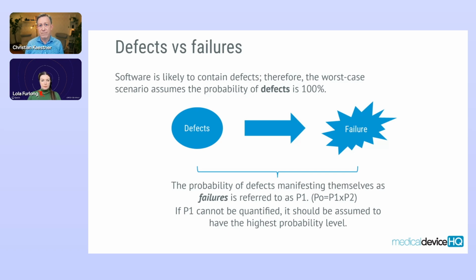The probability of defects manifesting themselves as failures is referred to as P1 when you work with risk management. Perhaps you're familiar with P1 and P2 concepts. If P1 cannot be quantified, it should be assumed to have the highest probability, meaning basically the worst case. And this is then, unfortunately, still 100%.